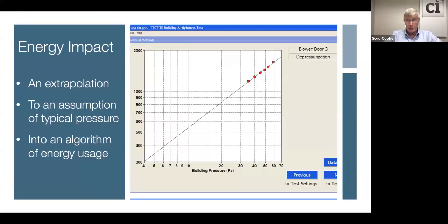that down to a pressure that would be considered more normal. And typically, depending on your climate zone, you're going to use 5 pascal or 10 pascal pressure. That is when you think about average wind pressures, stack effect, that is convection loops rising in air, mechanical pressures. ASHRAE has said 5 pascal is probably the right number.